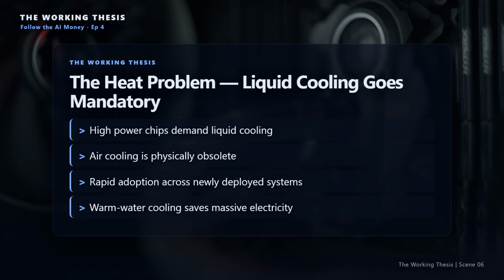This shift also saves massive power. Cooling is about 40% of a data center's energy footprint. Moving to direct-to-chip warm water cooling, using 45 degrees Celsius water, lets operators bypass energy-hungry chillers entirely. At a typical 50-megawatt site, warm water cooling saves over $4 million a year. Hyperscalers are adopting it because the efficiency gains directly impact their bottom line.